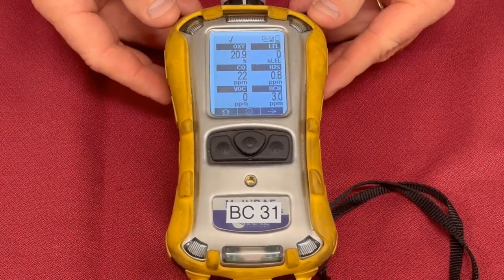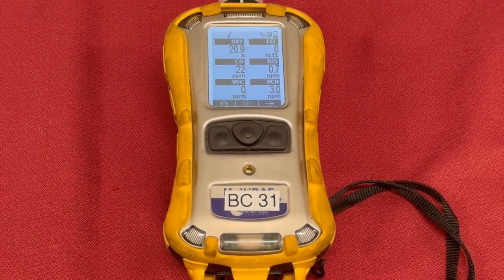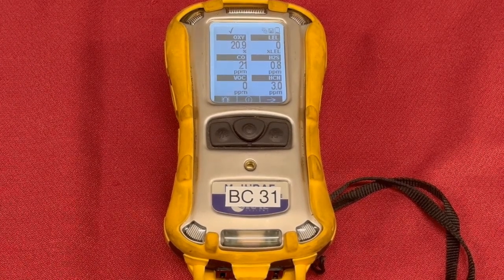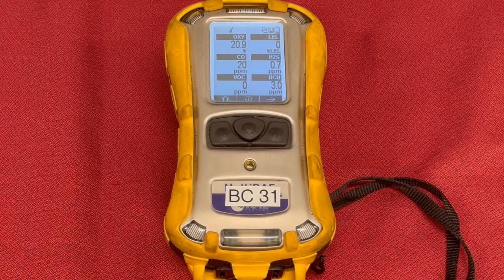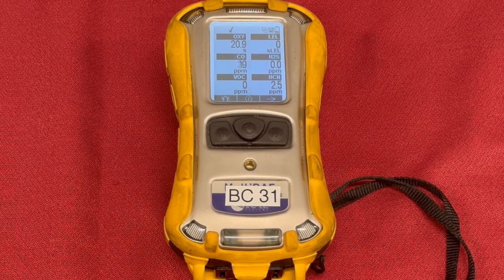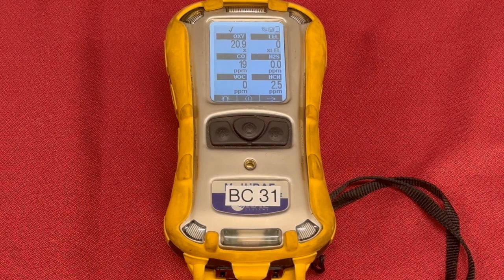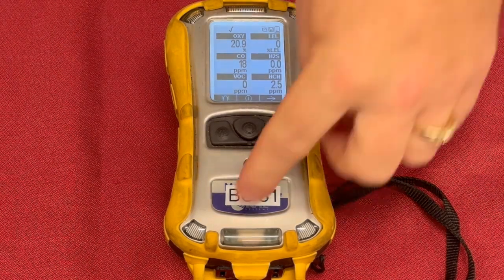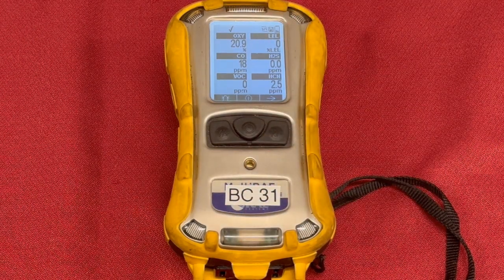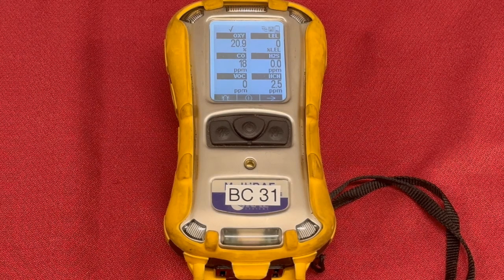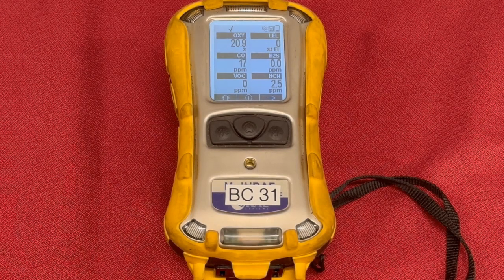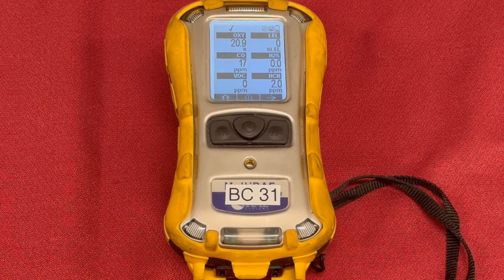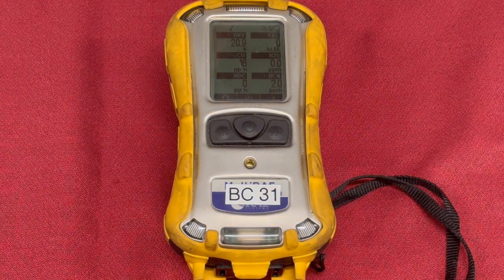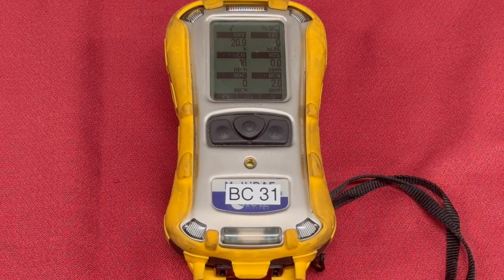Our first sensor we'll talk about is oxygen. I think everyone understands oxygen is very important. It's what allows human life to exist on the planet. So our meter is set to alarm in high oxygen and low oxygen both. If you get an alarm on the oxygen sensor, the whole meter will flash red around the lights, and then that sensor will alarm, telling you either you've got low oxygen or high oxygen. And obviously at that point, that's when you need to consider what's causing that situation. If it's low oxygen, you need to go ahead and use your SCBA and figure out what's displacing it. And if it's high oxygen, you probably have an oxidizer in the environment and a higher risk of fire. So you want to figure out what's causing that oxidizing to occur.